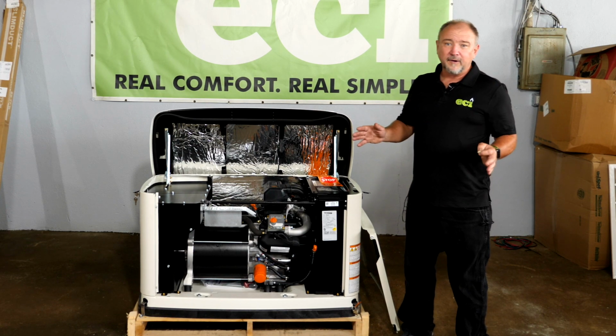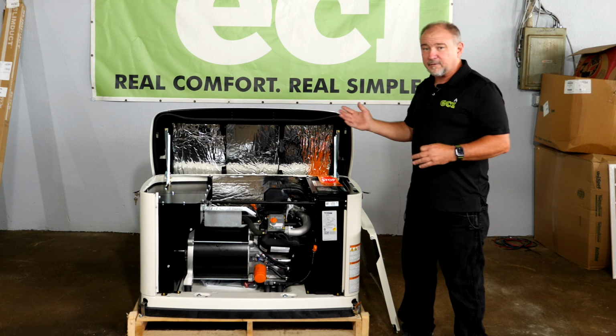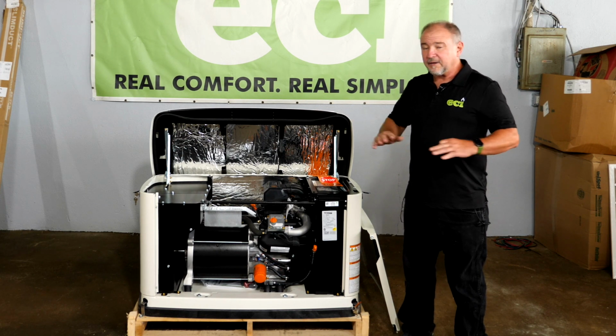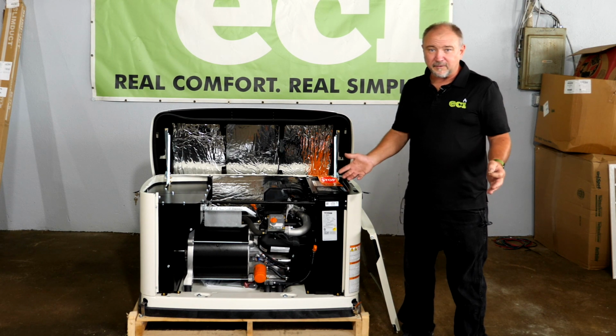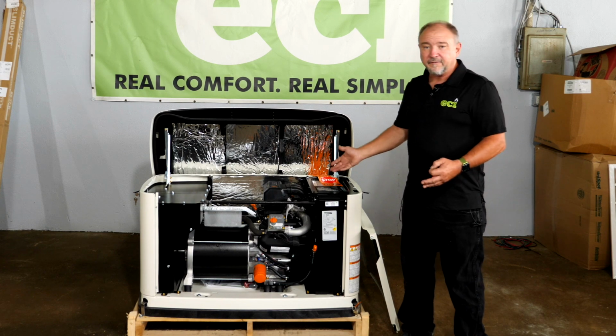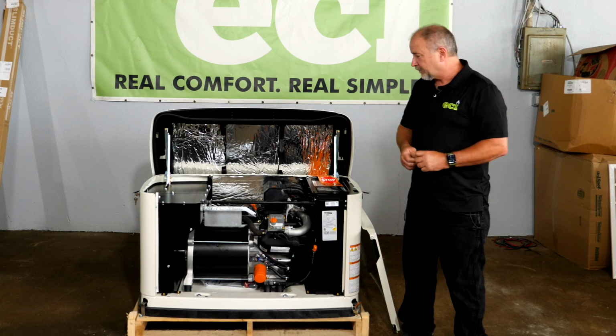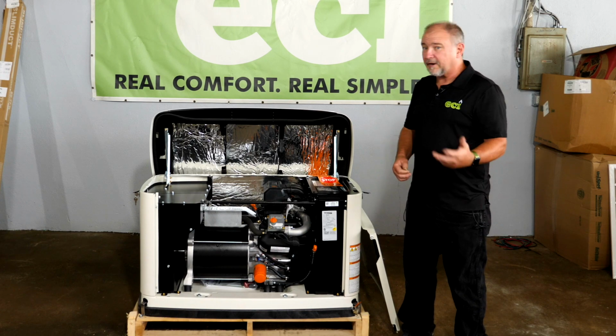There's no power interruption during this—it doesn't transfer the switch to generator power, so nothing is interrupted. It just starts the generator, runs a self-diagnostic, and shuts down. We can schedule this once a week or once every other week.